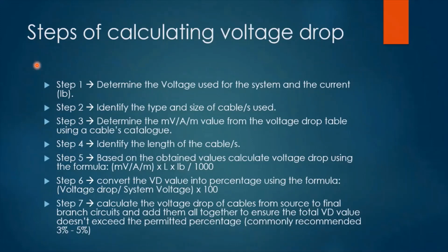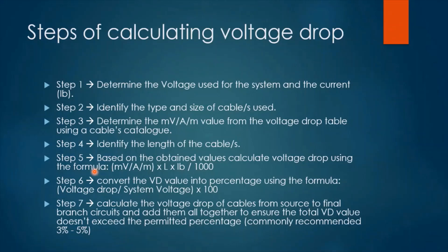Before we look at some examples, let's identify the seven steps of calculating voltage drop. Step one: determine the voltage used for the system and the design current (IB). Step two: identify the type and size of cable or cables used. Step three: determine the millivolt per ampere per meter value from the voltage drop table using a cables catalog. Step four: identify the length of the cable or cables. Step five: based on the obtained values, calculate the voltage drop using the formula.